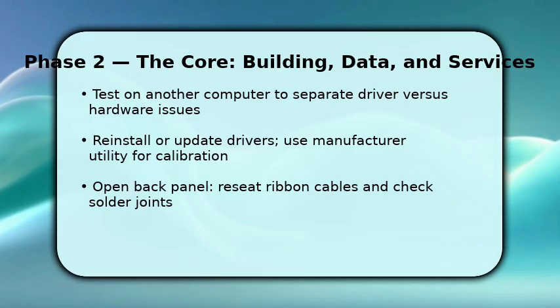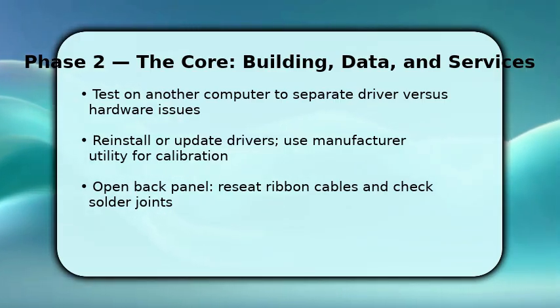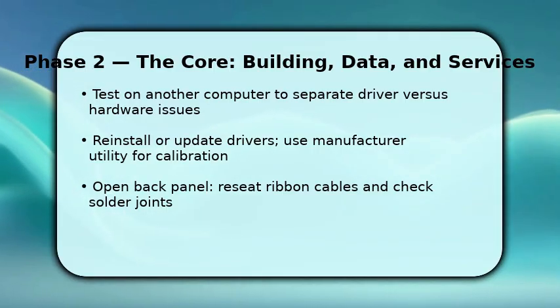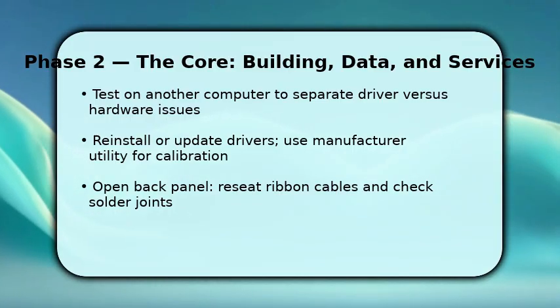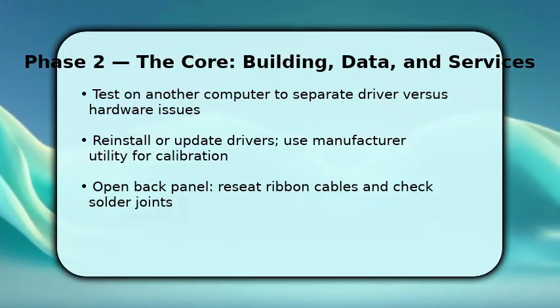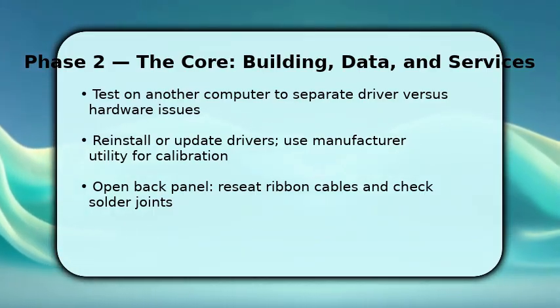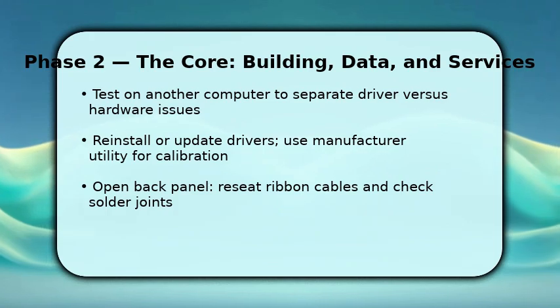Once done, power off and open the back panel carefully. Use an anti-static wrist strap, then reseat ribbon cables and inspect solder joints under light. If a loose connector is found, press gently to reseat, and if corrosion exists, clean with isopropyl and finish by reassembling the pad, power it up, and run the full calibration routine.